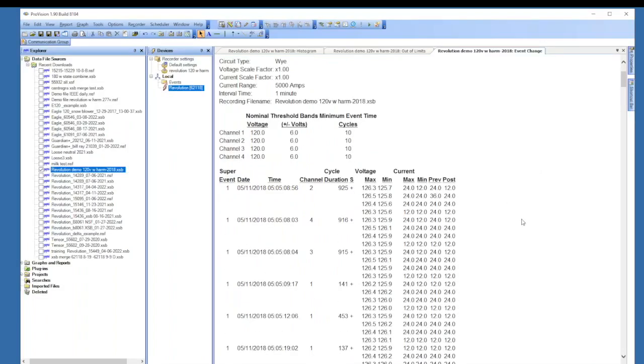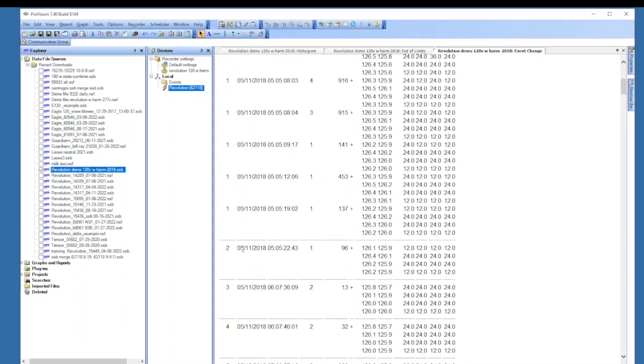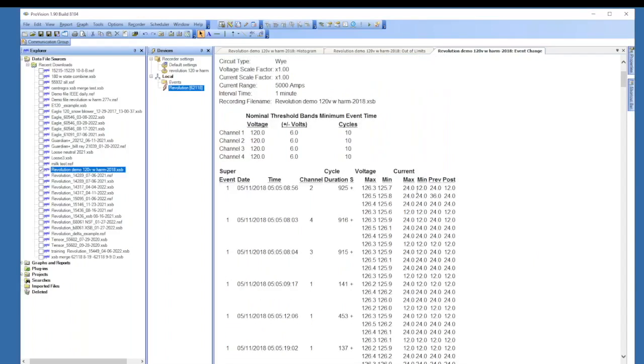The event change. Now in this one, we did go over 126 quite a bit, so if we're going to re-record it this time, we may want to adjust our plus or minus, maybe make it plus or minus 7, or maybe raise our 120 up to 122, something like that. But you can see that at this time, channel 1 for 96 cycles was outside, basically higher than 126. And this is channel 1, channel 2, channel 3, and channel 4. The min and max for the current is during those number of cycles, so during that event. Previous is what the current was before, and post is what it was after.